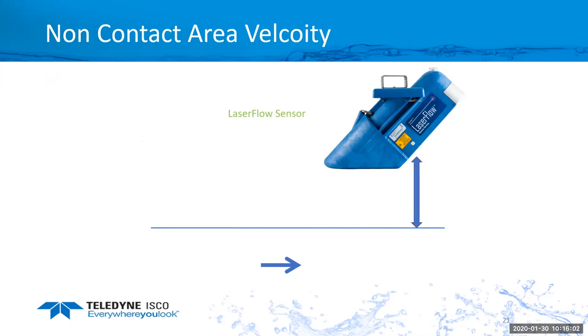It uses an ultrasonic sensor to read the distance to the surface of the water. When we know the distance, the laser will focus below the surface of the water. The laser is on for about 2 seconds and takes 5,000 spectral readings to get our velocity.